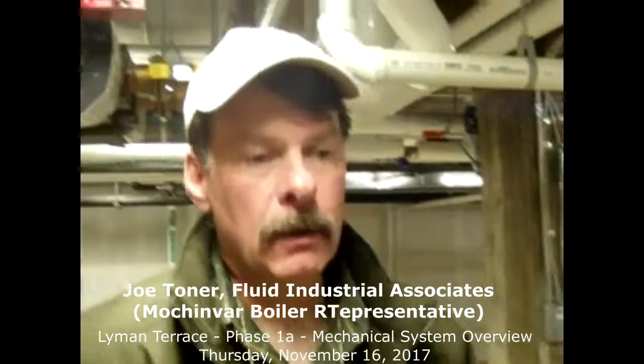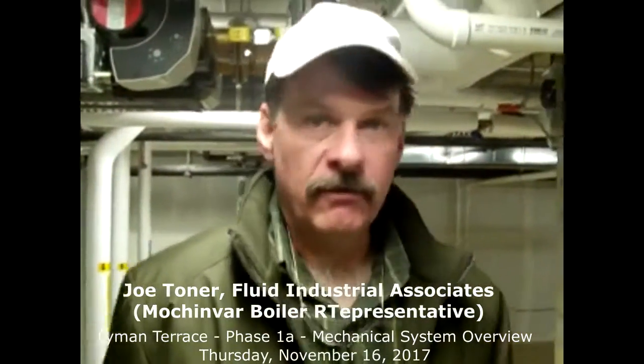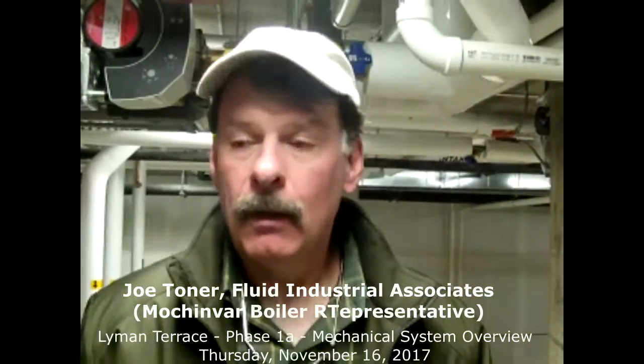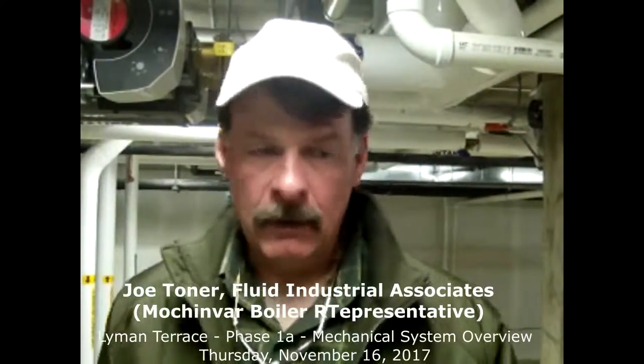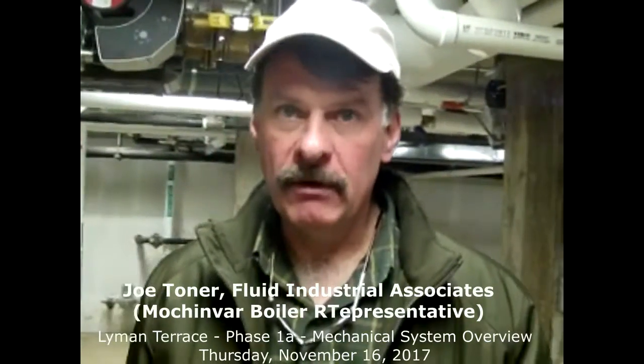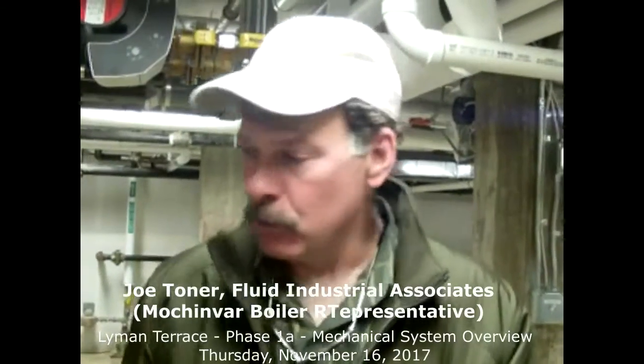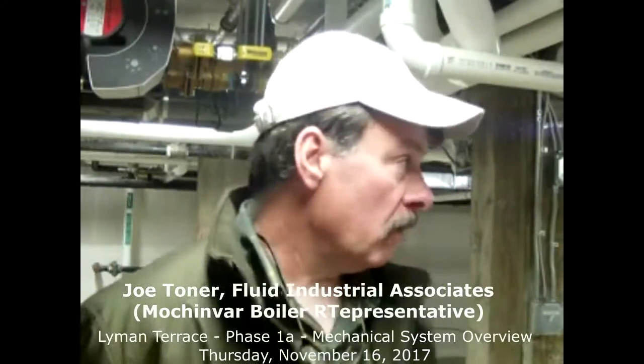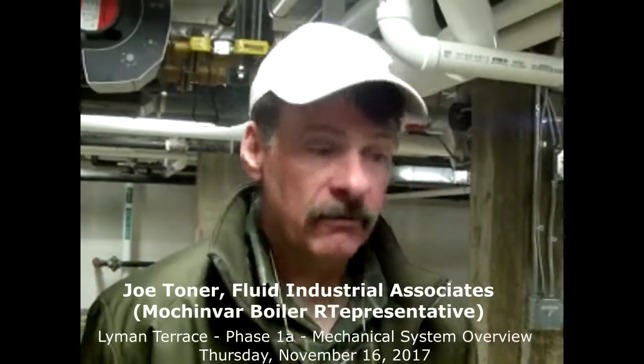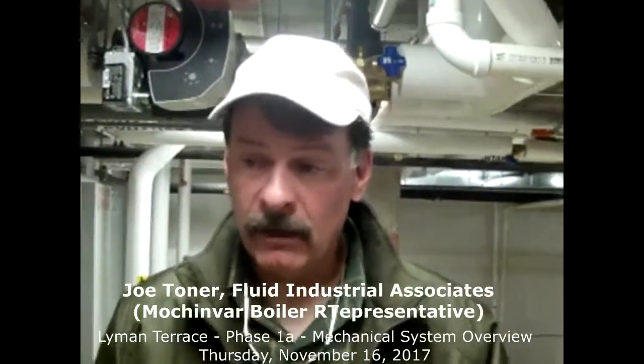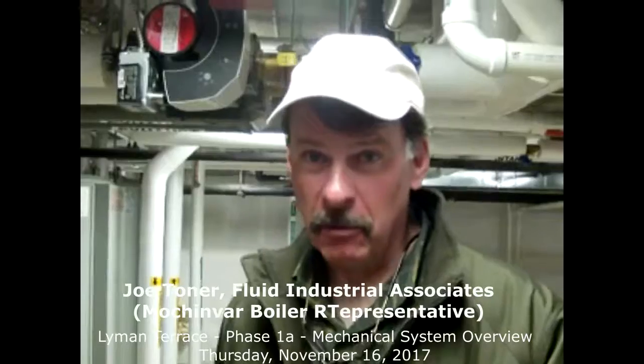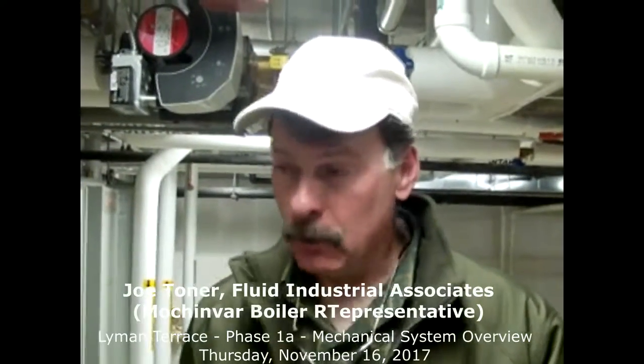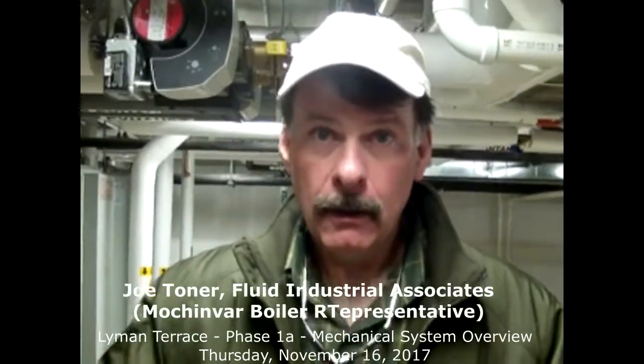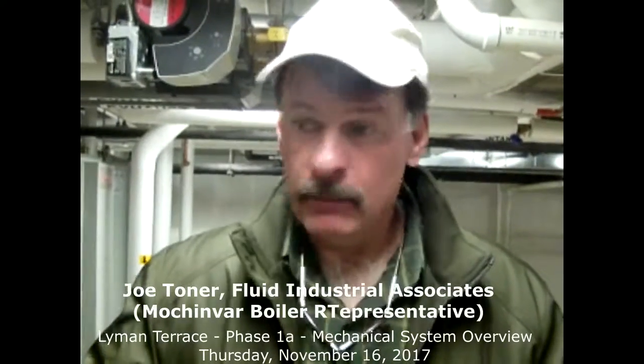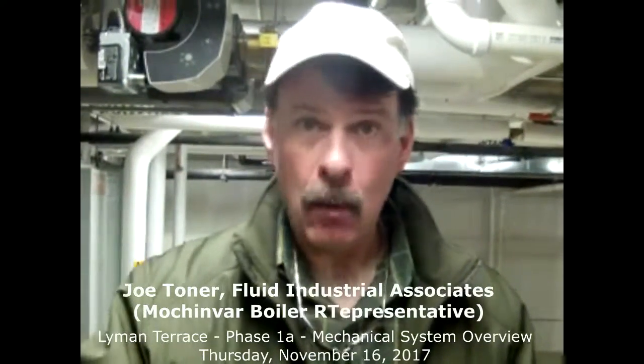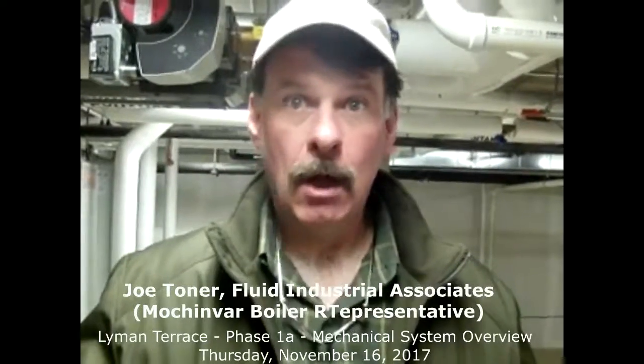It's important that somebody does a visual here once a week, once a month, because I'm not sure, you know, John used the term earlier of 100% redundancy. That may be true, and if it is, it becomes even more important to get a visual in here, because we've had this happen before in mechanical rooms that don't get checked with multiple boilers that can communicate with one another. You could have a problem with one boiler, and it would be off. Nobody knows, because nobody's checking it. If it's truly 100% redundancy, that one boiler that's still running could carry the load, all doing great on the coldest day of the year.